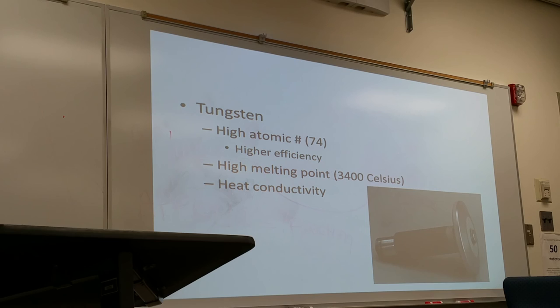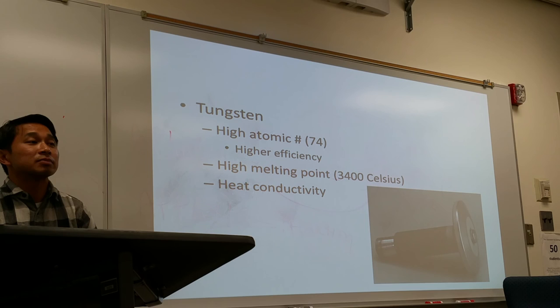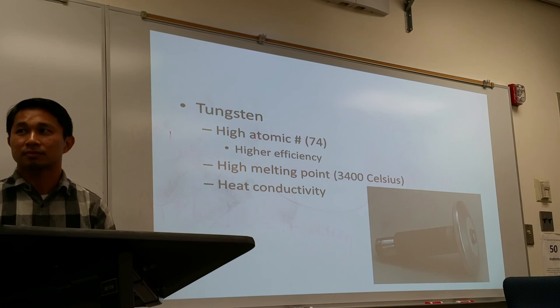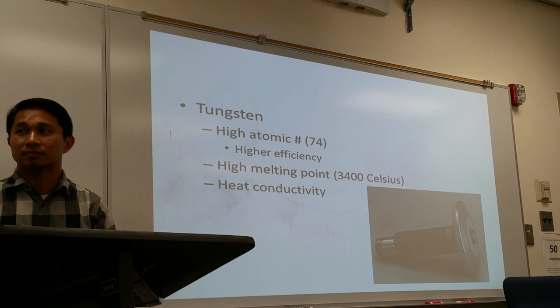Why tungsten? Because it has a high atomic number — 74 — which makes it very efficient for x-ray production. Another factor is that tungsten has a very high melting point of approximately 3,400 degrees Celsius. The production of x-rays generates a lot of heat, and tungsten's high melting point helps it withstand that. Tungsten also has high heat conductivity — it absorbs heat easily and releases it fast.